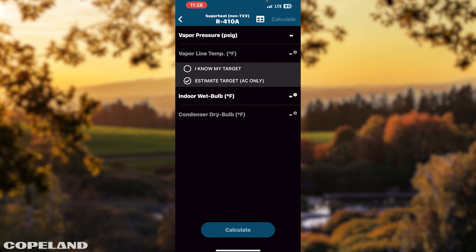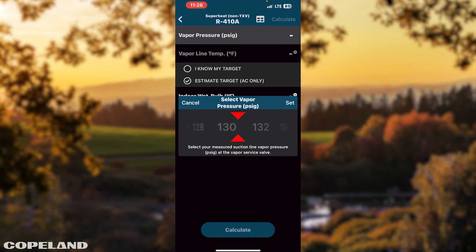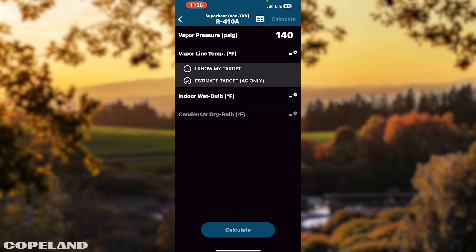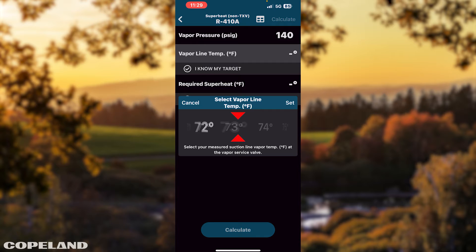Next, select Superheat. Tap Vapor Pressure. Scroll left or right to select your pressure, then tap Set to enter your pressure. Determine if you know your vapor line temperature by selecting I know my target or estimate. Then tap Vapor Line Temperature. Scroll left or right to select your temperature, then tap the Set button.